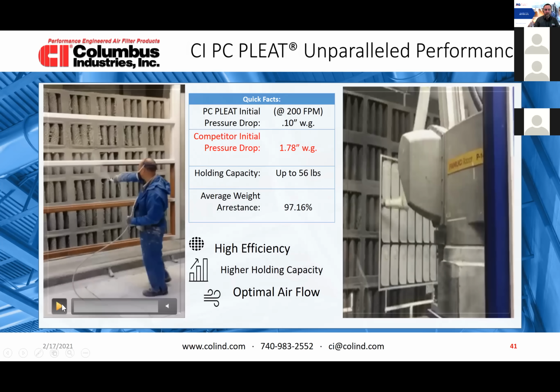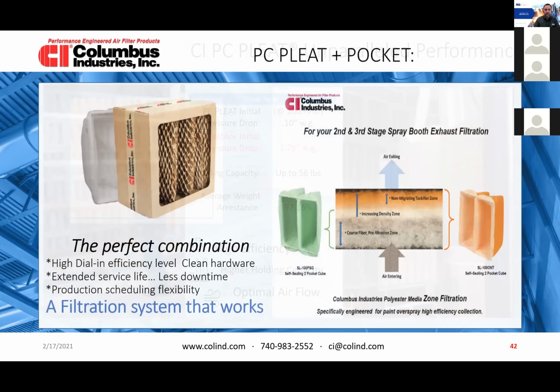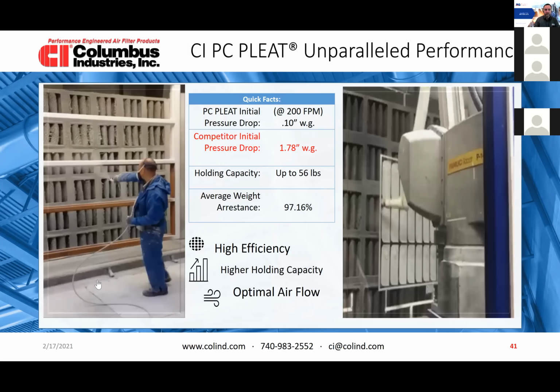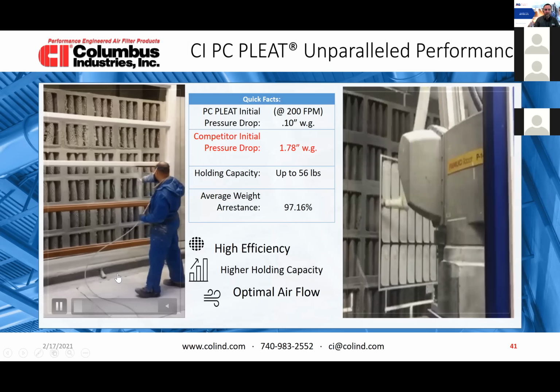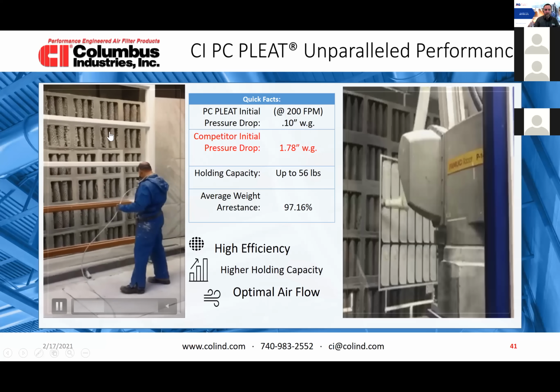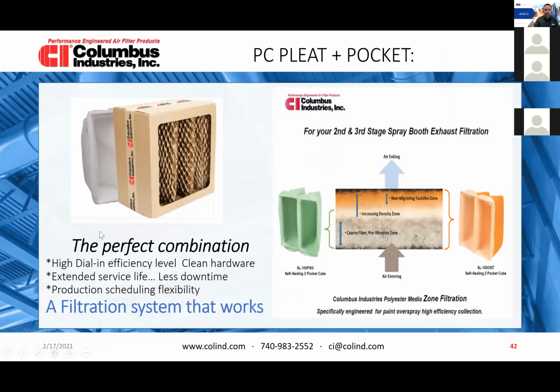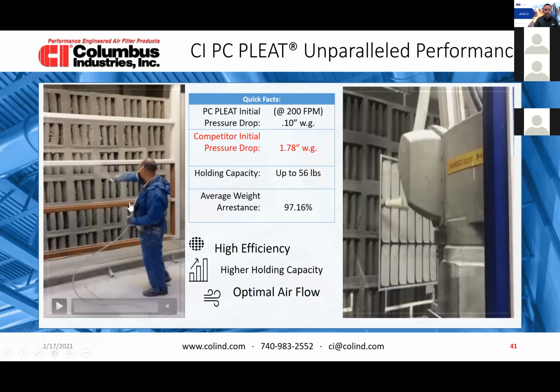Wood industry, as you can see, manual spray. I'll go back to that. Every time I put the video on, something happens there. What I'd like you to notice, besides the guy painting, is that the filters on top here are more loaded than the bottom. The reason is these filters probably were changed like a week ago.